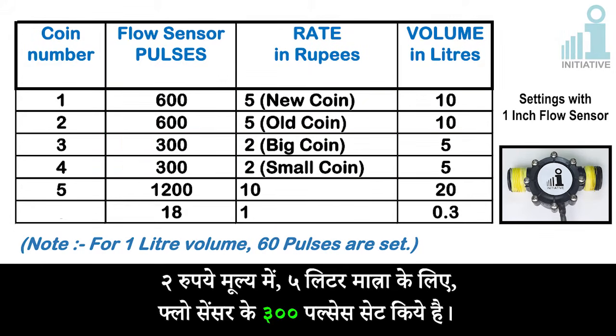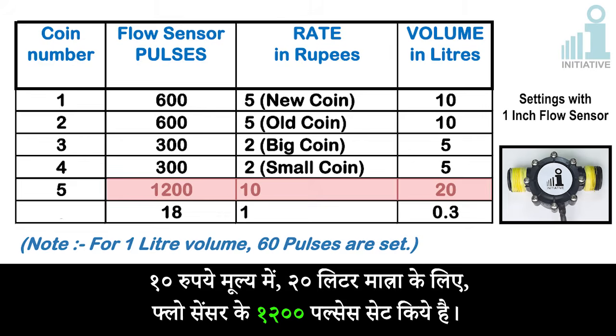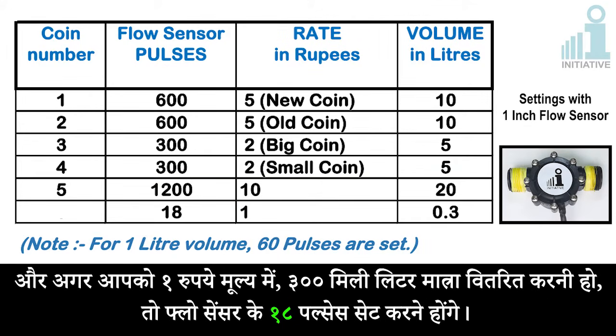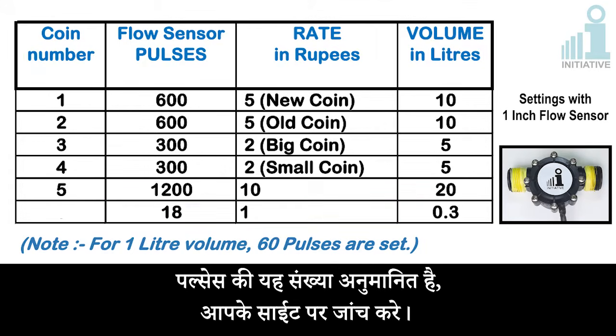And for the rate of 2 rupees and 5 liters of volume, 300 flow sensor pulses needs to be set. And for the rate of 10 rupees and 20 liters of volume, 1200 flow sensor pulses needs to be set. And for the rate of 1 rupee, if you want to dispense 300 milliliters of volume, then 18 flow sensor pulses needs to be set. All these pulses counts are approximate. You have to verify at your site.